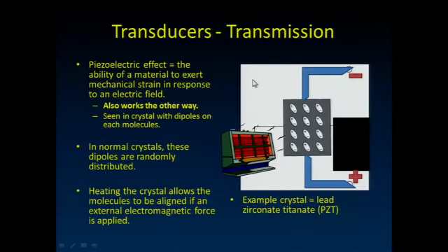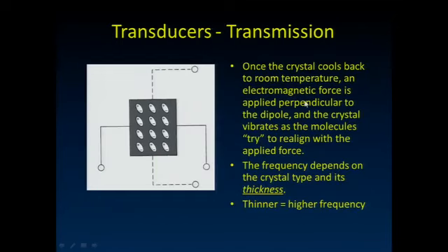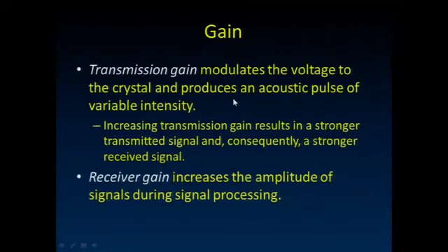So the transducer is made out of this piezoelectric crystal material, right? And if I apply a voltage across it, it deforms that crystal, it changes its shape, if you will, just like a speaker. As we apply that voltage, the cone in that speaker moves in and out. The same thing, this piezoelectric crystal is going to change its shape. So we're going to use that to apply that voltage at a particular current, at a particular frequency, to deform that crystal and propagate the sound.